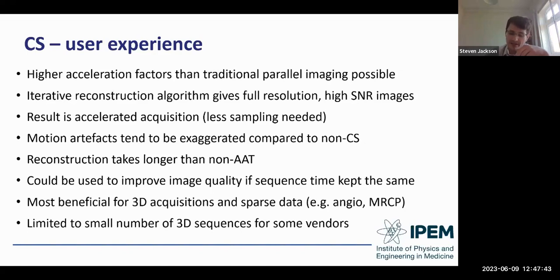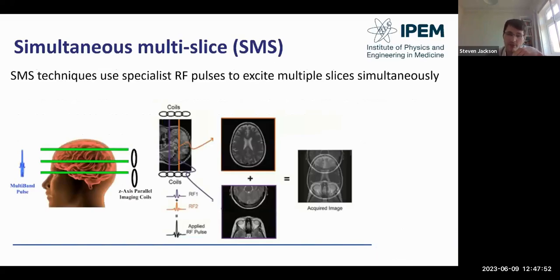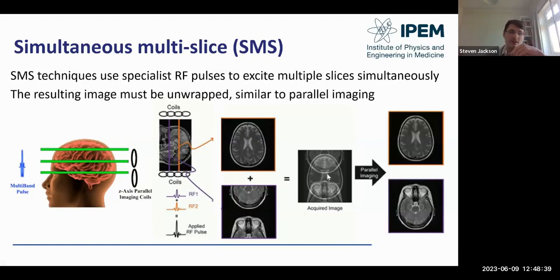Moving on to simultaneous multi-slice: SMS techniques use specialist RF pulses to excite multiple slices simultaneously. The applied RF pulse is essentially the sum of two RF pulses exciting two different slices of tissue. The RF pulses are specially adapted so that one slice reconstructs in the familiar way while the other reconstructs with a field-of-view shift, appearing as two different isolated areas of signal superimposed on each other. An unwrapping algorithm similar to parallel imaging is then used to separate them into two separate slices that can be written to DICOM and reported on.